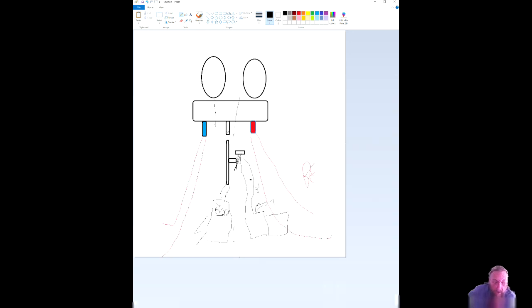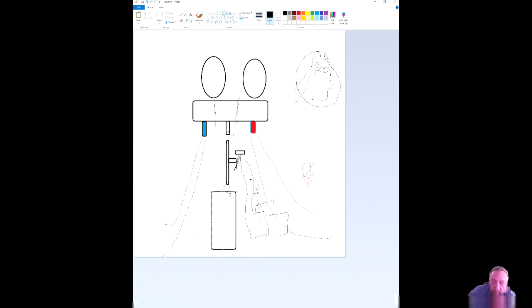While I'm pulling a vacuum, well, actually, I'm sorry, I switched. My vacuum pump is on the hose, on the shutoff here. The micron gauge is here, and my vacuum pump is here. I'm sorry, this wasn't what I planned to talk about, so I wasn't prepared for it. So this is where my vacuum pump is. And when I reach 500 microns, I shut this off here. Now my micron gauge is still connected to my refrigerant system, but I'm pulling my vacuum here.